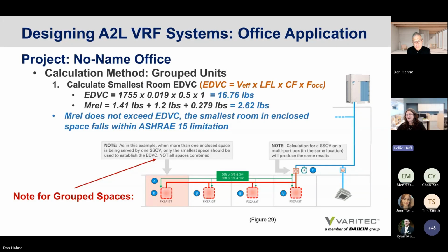Right. And as designers, how can they estimate charge in the VRV system for the pipe volume contribution? That would be done in the selection software. At least from Daikin's standpoint, all that is done as part of the selection software process. As I said earlier, you're just inputting the distance from the shutoff valve or the BS box to the indoor unit, and the indoor unit will already be part of the initial design of that system, so you know what size that indoor unit is. With that information, the software will be able to calculate the rest, so that is the MREL. That's something, Jordan, that your outside sales person would be able to help you run through.